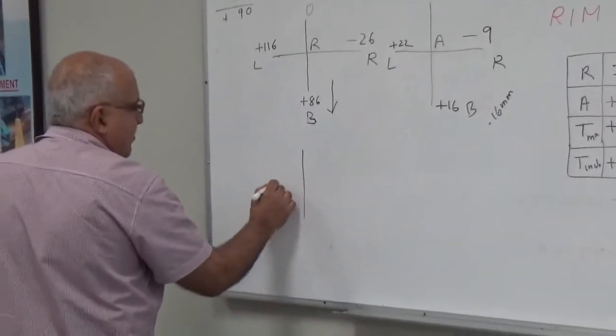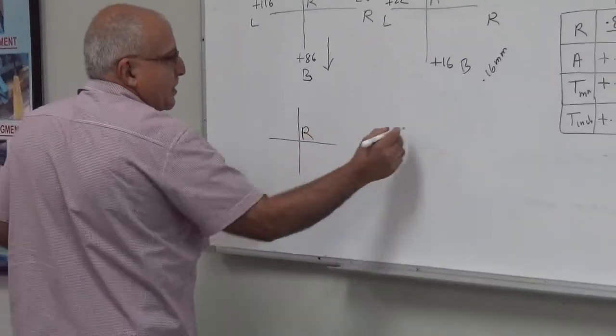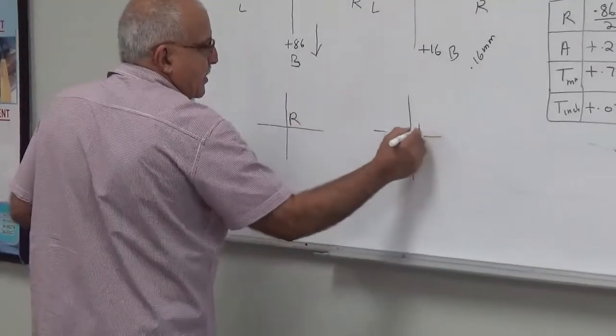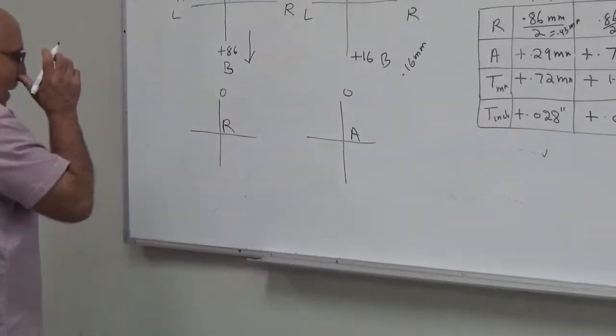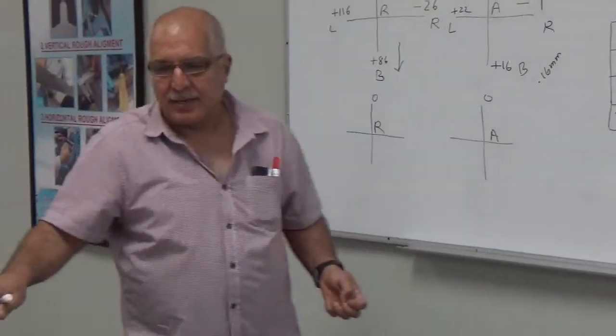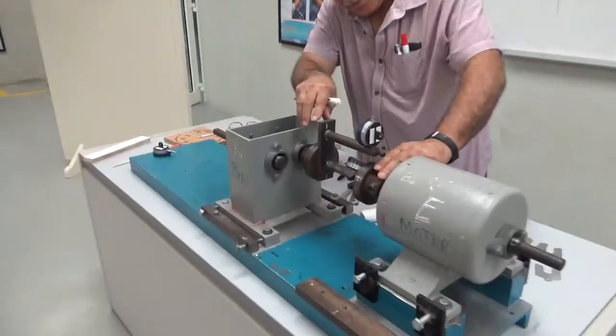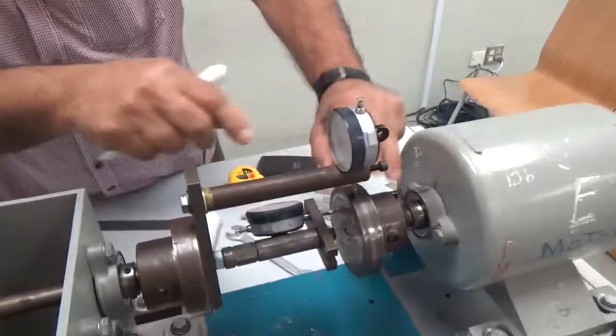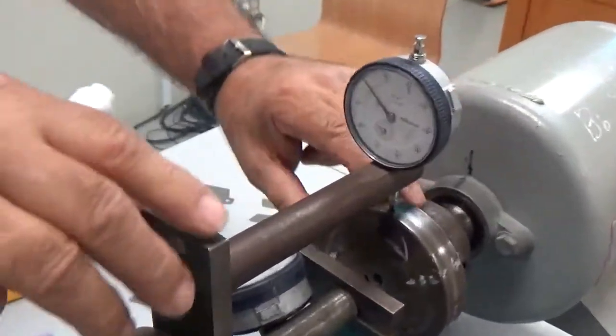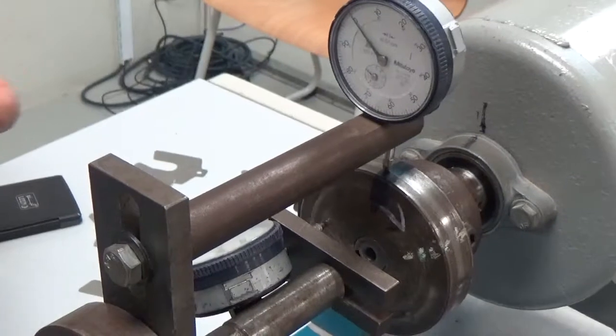Okay, so these readings will be after making alignment. This is radial, this is angular. So let us start here. Now this one is zero here, I made this zero. Now on the top I will go here.